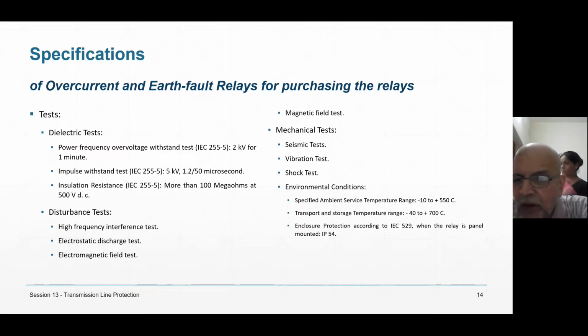Transport and storage temperature minus 40 to plus 700. Enclosure protection is required. Enclosure protection means the relay is kept in a very bad environment, very high temperature, very low temperature. There will be dust, and deliberately conducting powders. IP54 is the worst environmental standard, and relays have to pass that.